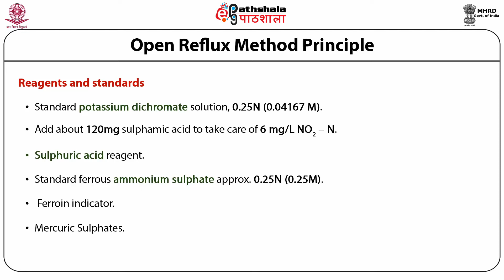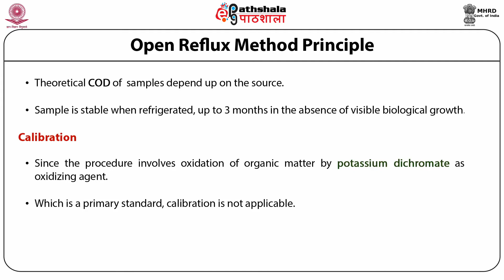The theoretical COD of the samples depends upon the source of the sample, either it will be tap water or industrial wastewater, and which type of industry it is. So the value of COD depends on which type of sample we have taken for the COD test. The sample is stable when refrigerated up to 3 months, in the absence of visible biological growth. For the COD determination, calibration is not required, since the procedure involves the oxidation of organic matter by potassium dichromate as an oxidizing agent, and it is considered a primary standard, so calibration is not applicable for that particular test.